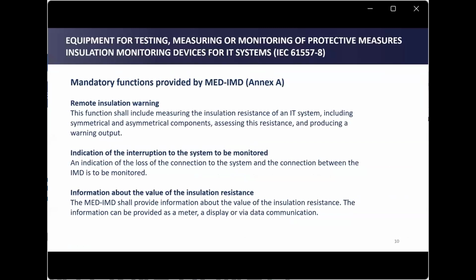Remote insulation warning. This function shall include the measurement of the insulation resistance of an IT system, including symmetrical and asymmetrical components, and assessment of this resistance and a warning output. Indication of the interruption to the system to be monitored: an indication of the loss of the connection to the system to be monitored and of the connection between the IMD. Information about the value of the insulation resistance. The MED-IMD shall provide information about the value of the insulation resistance. The information can be provided in form of a meter, a display, or via data communication.